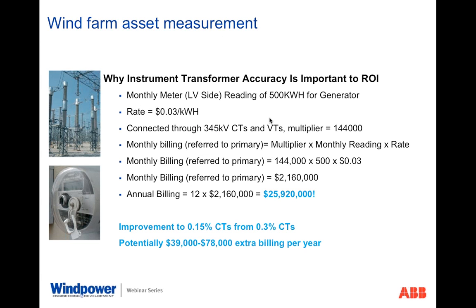Here's a quick calculation for a relatively large wind farm being metered on the high voltage side with those 345 kV CTs and VTs in the upper left-hand photograph, tied to the meter down here in the lower left-hand photograph. In this case, you've got 500 kilowatt hours monthly meter reading going into the meter, which is the low voltage side of the instrument transformers. That's not the primary side.